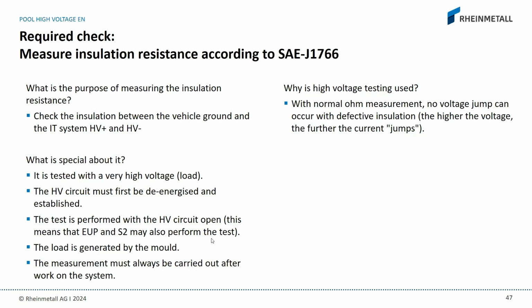How do we control this? It's pretty much the same as a water hose. Let's say we have a small damage on the isolation. We need some high voltage load, some pressure, to see the drop out of electrical current, the same way we see on a water hose: if you put pressure on the hose, the pressure finds a small hole and the fluid goes through. The same thing happens on the electrical side.